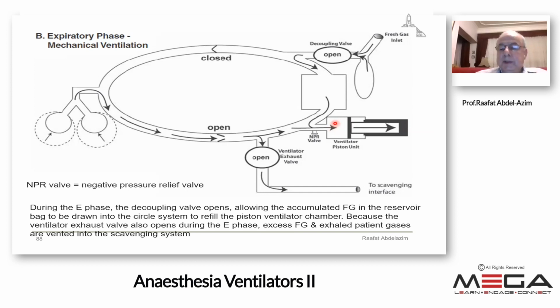So this one will be filled with the expired patient's gas, in addition to what is coming through the open decoupling valve, adding from the fresh gas flow and the reservoir bag. So the reservoir bag will be deflated during expiration. Both the patient's lung and reservoir bag will be deflated during expiration. So what is done for the fresh gas decoupling system is having a piston instead of a bellows assembly, and the addition of the fresh gas decoupling valve that closes during inspiration and opens during expiration.